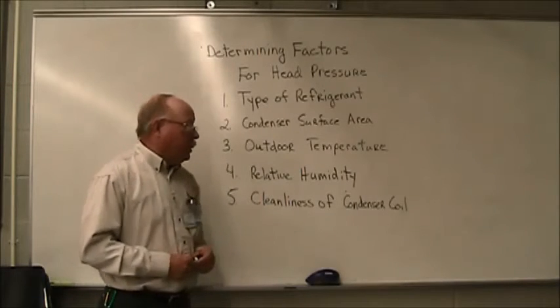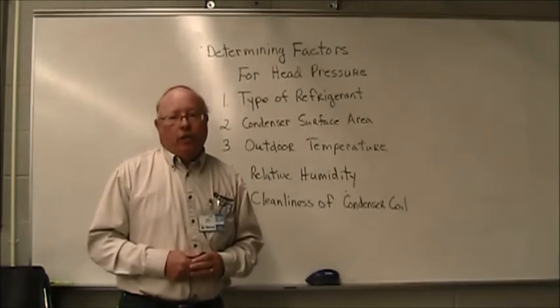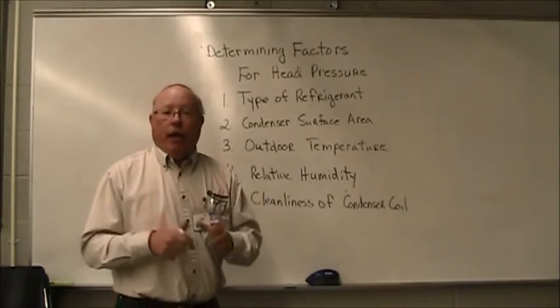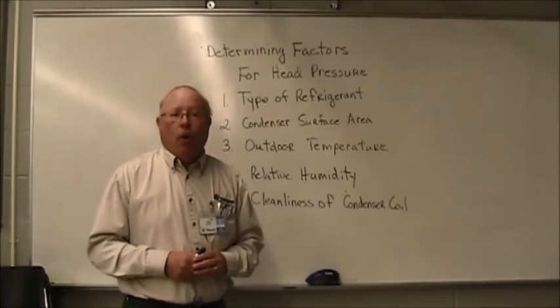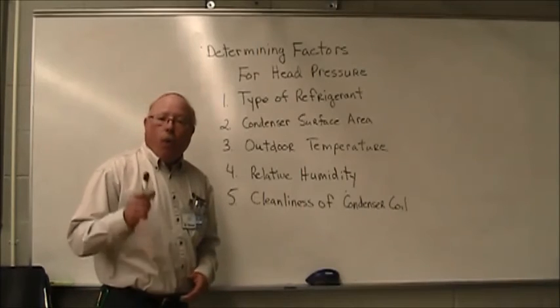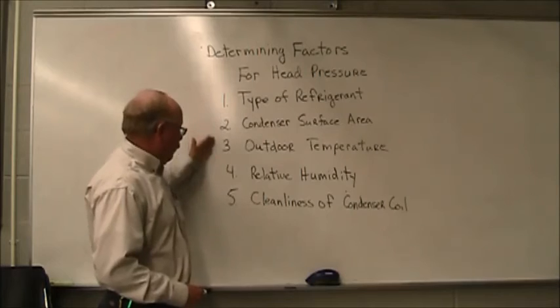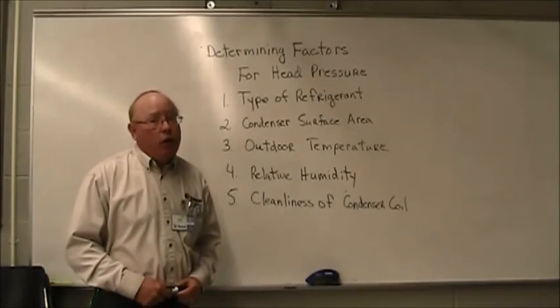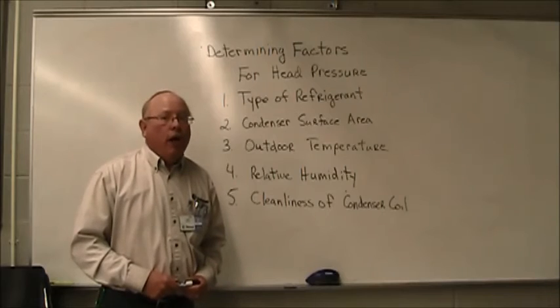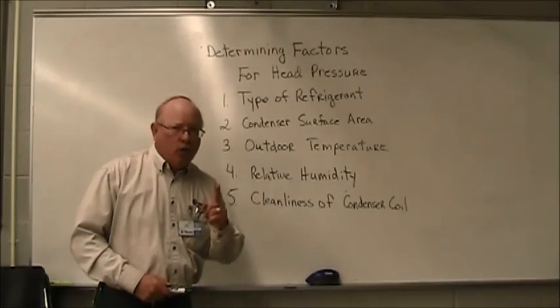And then of course the cleanliness of the condenser coil — is it clean or is it dirty? A dirty coil will give you a higher head pressure. A clean coil will give you a lower head pressure. So when thinking about what the head pressure should be on a unit, we should always look at these five items because they're going to be the determining factors that determine what your head pressure is going to be on any given day. This is the 2 Minute Tutor.